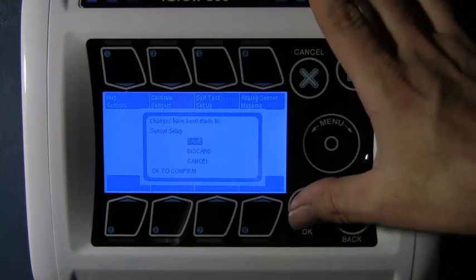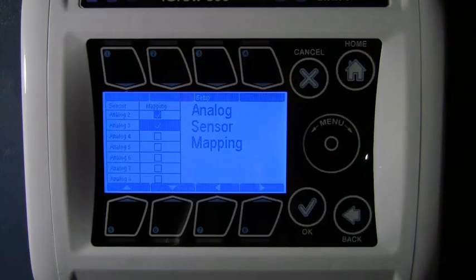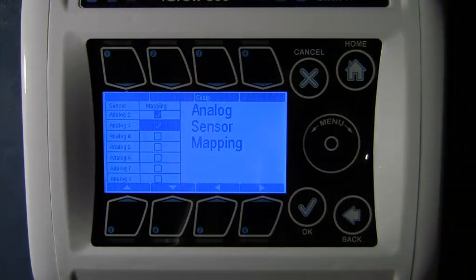Now, if you were to go ahead and go into analog sensor mapping, this section enables the user to average the data from separate analog sensors. This is useful in situations where the user needs to take temperature data from multiple locations in a zone and then average them to form an accurate temperature reading from an entire zone.